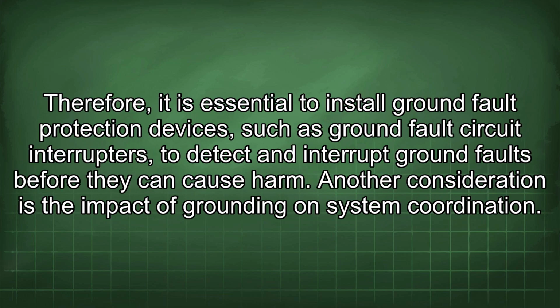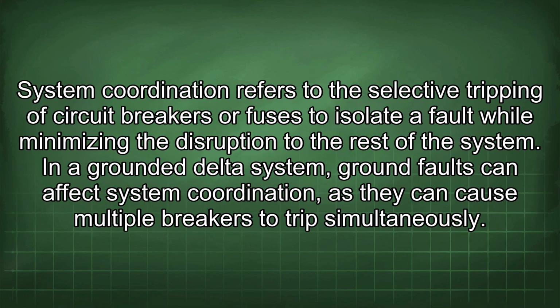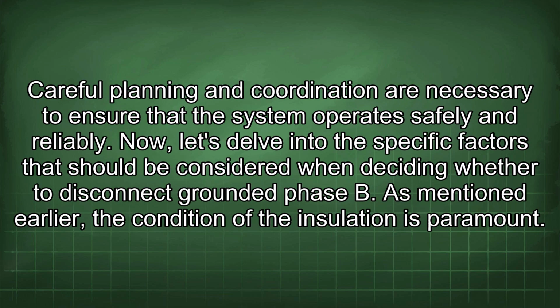Therefore, it is essential to install ground fault protection devices, such as ground fault circuit interrupters, to detect and interrupt ground faults before they can cause harm. Another consideration is the impact of grounding on system coordination. System coordination refers to the selective tripping of circuit breakers or fuses to isolate a fault while minimizing the disruption to the rest of the system. In a grounded delta system, ground faults can affect system coordination, as they can cause multiple breakers to trip simultaneously. Careful planning and coordination are necessary to ensure that the system operates safely and reliably.